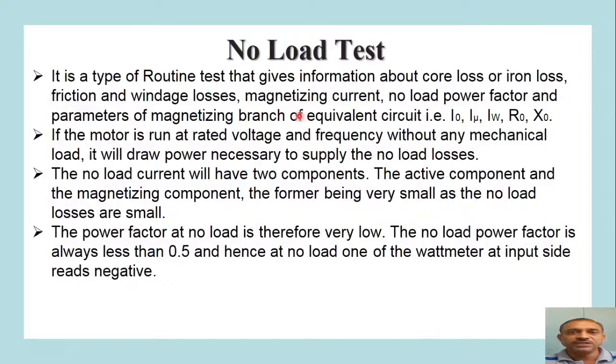Now let us first discuss the basics of the no load test. The no load test is a routine test that gives us information about the core loss or iron losses, then the mechanical losses which include the friction and windage loss. Also this test gives us data regarding the magnetizing current, the no load power factor, and the parameters of the magnetizing branch of the equivalent circuit of the induction motor, that is I0, IMU, IW, R0 and X0.